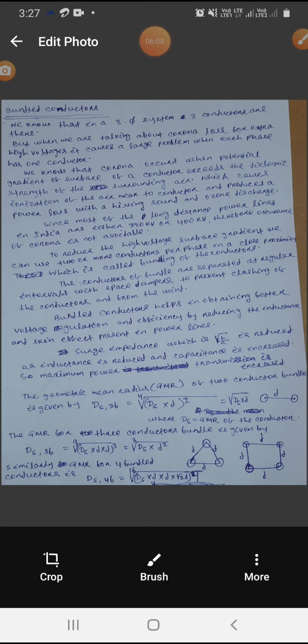For that, Ds3b is the 9th root of Ds into d whole cubed, that is equal to the cube root of Ds into d squared. Similarly, we can calculate the GMR for four bundled conductors. When each and every phase of the transmission line has four bundled conductors, then Ds4b is equal to the 16th root of Ds into d into root 2 d whole to the power 4. When we simplify it, Ds4b becomes 1.09 into the fourth root of Ds into d cubed.